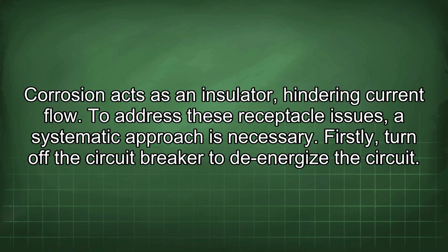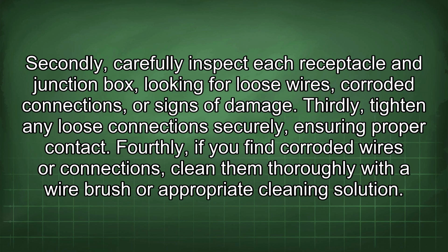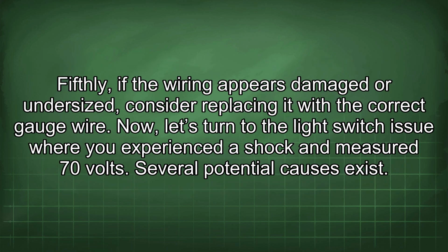To address these receptacle issues, a systematic approach is necessary. Firstly, turn off the circuit breaker to de-energize the circuit. Secondly, carefully inspect each receptacle and junction box, looking for loose wires, corroded connections, or signs of damage. Thirdly, tighten any loose connections securely, ensuring proper contact. Fourthly, if you find corroded wires or connections, clean them thoroughly with a wire brush or appropriate cleaning solution. Fifthly, if the wiring appears damaged or undersized, consider replacing it with the correct gauge wire.